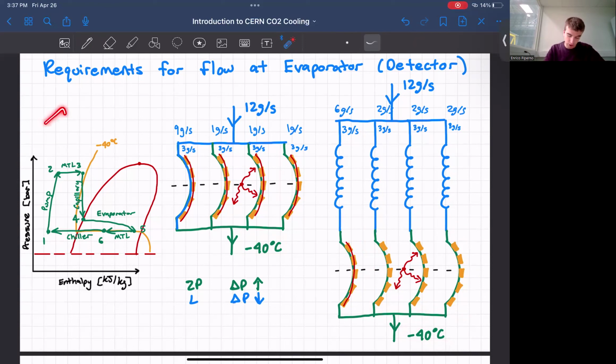Looking at this pressure-enthalpy diagram on the left, which we drew in the last video, after the chiller we're at point 1. And in theory, we could go from point 1 to point 4. However, as we saw, this is very sensitive to a single evaporator failing. As a result, we increase the total pressure of the refrigerant and then drop the pressure with the capillary.